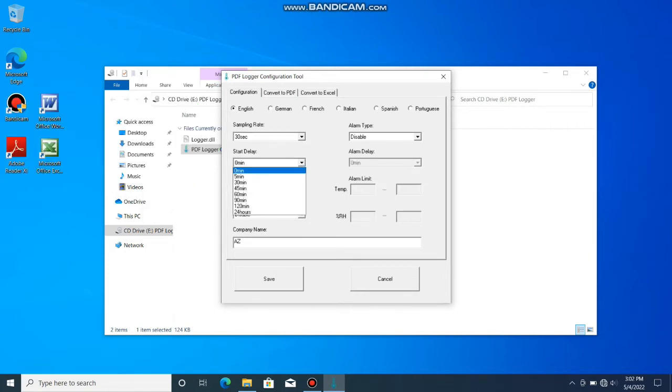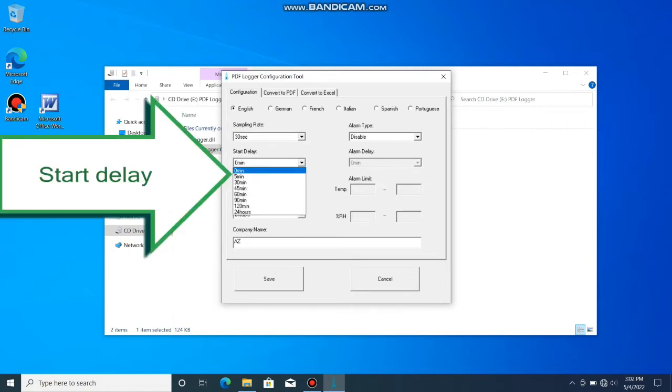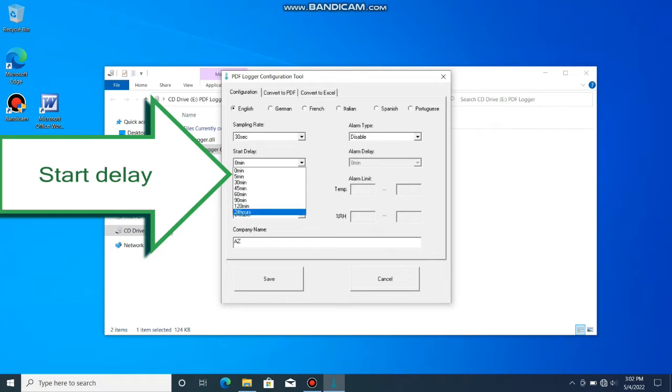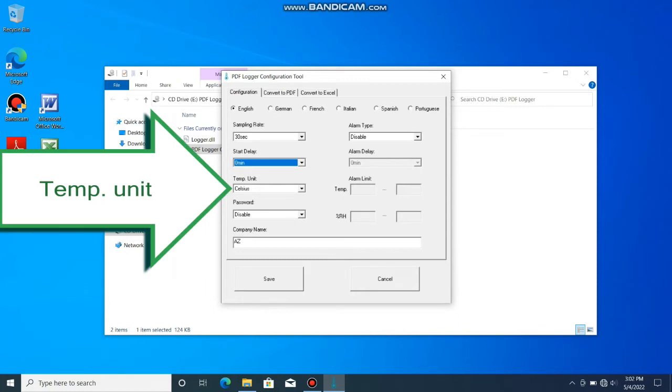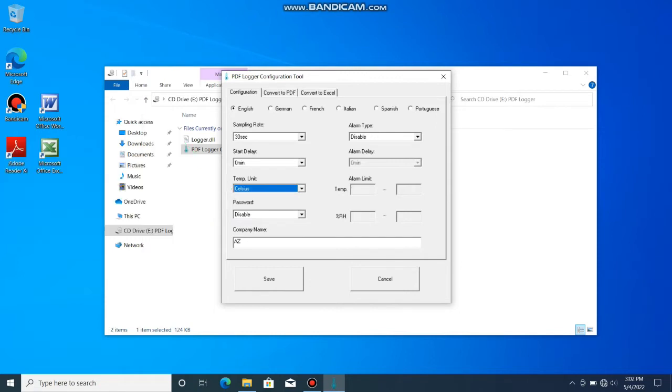Select the sampling rate. A 30 seconds rate can give this logger 8 days recording time. Start delay can be programmed when you want to take the first reading some minutes after the recording function is activated. Select the temperature unit that you prefer to read on LCD and report.